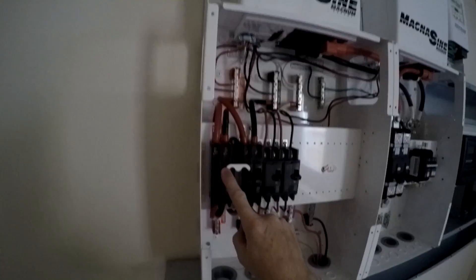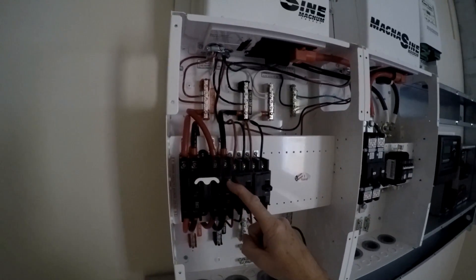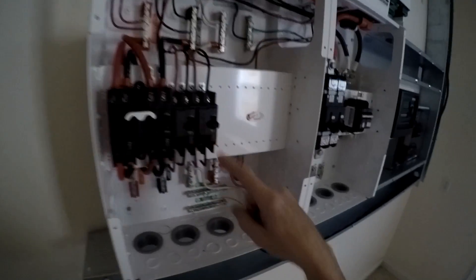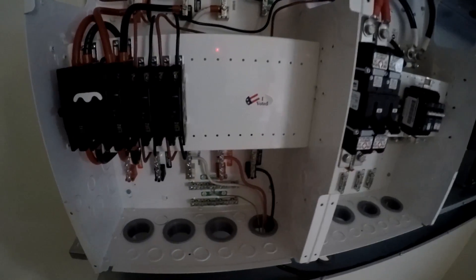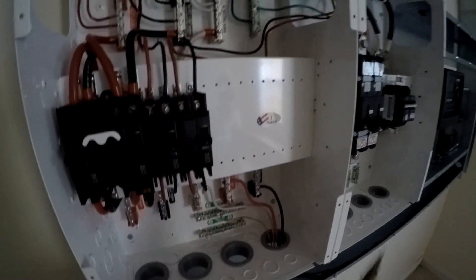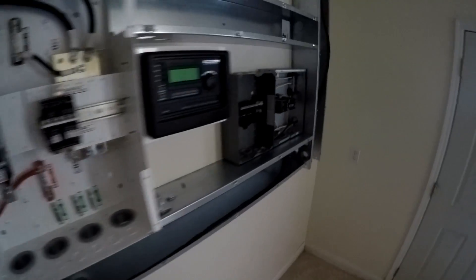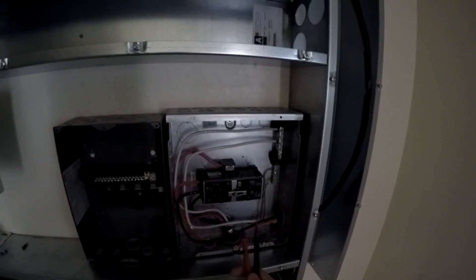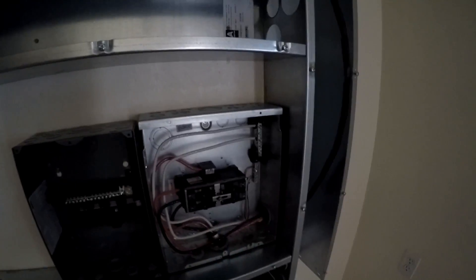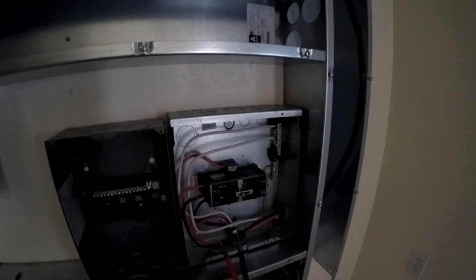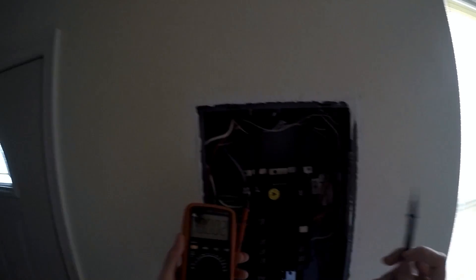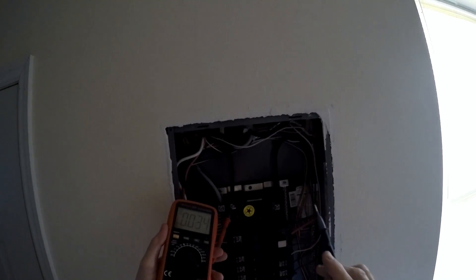I've got my AC bypass off. This is the power to the inverters, it's off. It's gonna stay off for a long time. This is the AC input which we're gonna get hot pretty quick. This is the transfer switch, everything's turned off. Follow that over to here, this is my 60 amp output breaker and that's turned off.